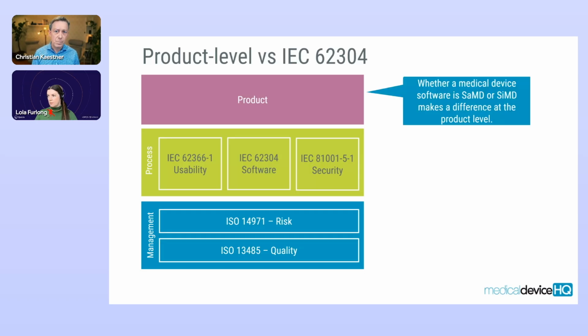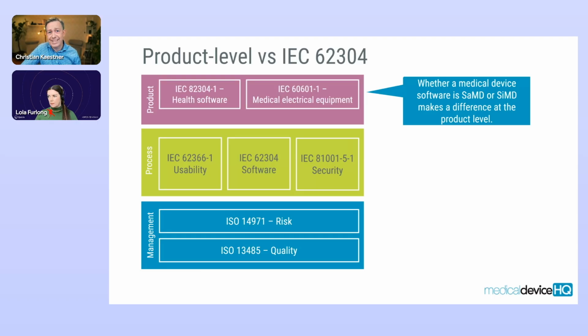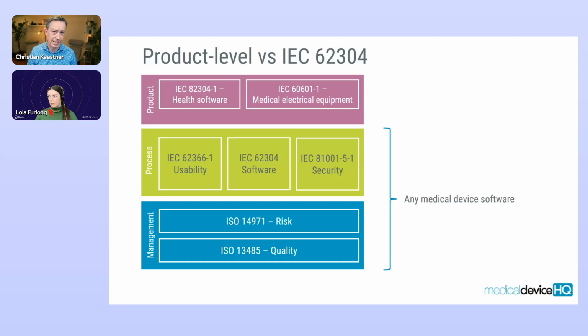At the product layer, it matters whether it's a SaMD or SiMD, as this would guide the choice of standards. If you're developing a standalone software SaMD, your go-to product standard is IEC 82304-1. If you're working with embedded software or SiMD, software in a medical device, the product standard is likely IEC 60601-1 or perhaps IEC 61010-1. However, being 20 years old and written before SaMD, cloud, and AI, the current version is biased towards SiMD terminology and examples, and I think that's excusable given the age of the standard.